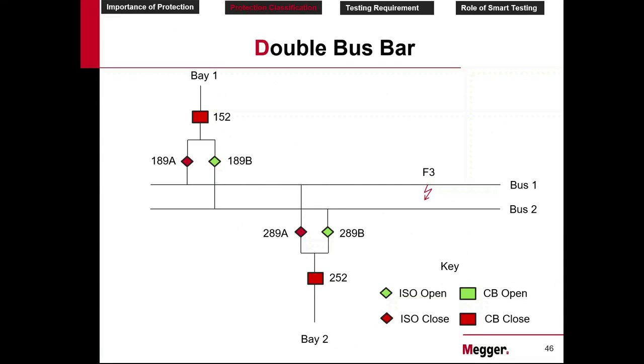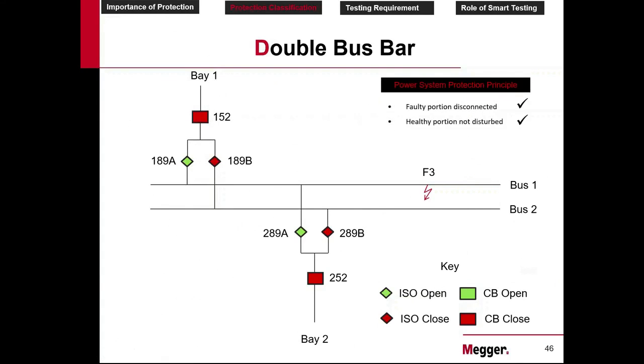Now what happens? Can I open this 189A and 289A? We cannot open it because it's an isolator. An isolator is an offline device. We can only open the breaker. Therefore, we have to trip the breaker. Still, we have disturbed. Okay, so now we can open this isolator, close this isolator, and then close the breaker. Now what happens? Bay 1 is healthy. Bay 2 is healthy. Bus 1 is faulty. Yes, we have isolated it and we have shifted to bus 2. Thus satisfying both the principles.